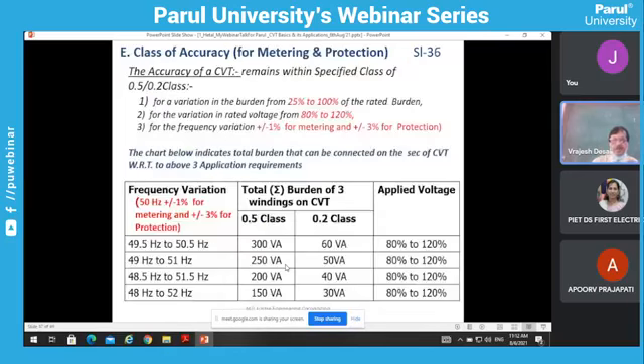Now in total, as a summary of this, there are three things we have to see. The CVT is, as you know, sensitive to the frequency, because the CVT is tuned at 50 hertz in the laboratory because we have to compensate the capacitive components with respect to inductive components so that the phase angle always remains very near to zero. And also there is a voltage variation in the system. Here, the voltage variation range is from 80% to 120%. Frequency is plus minus 1% for metering and plus minus 3% for protection. And again, the burdens also vary. Suppose you have 30 VA, but it may happen that in some location the VA burden is just 25%, that is 7.5 VA. So the accuracy has to be maintained at both the burdens, that is for 7.5 VA as well as 30 VA.